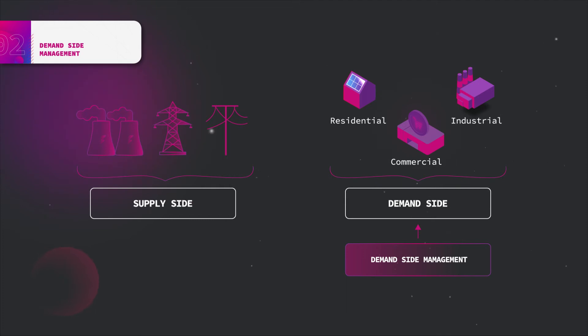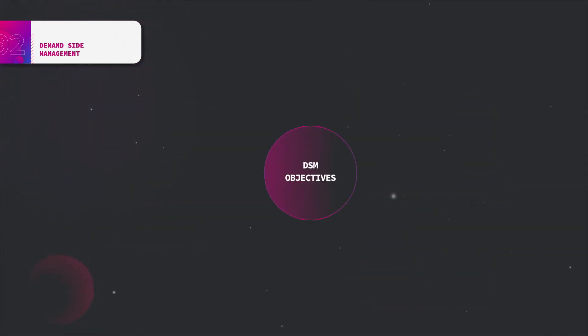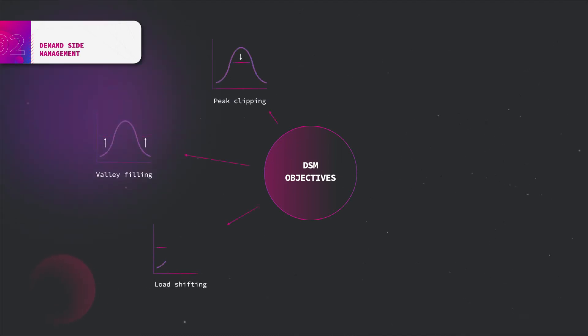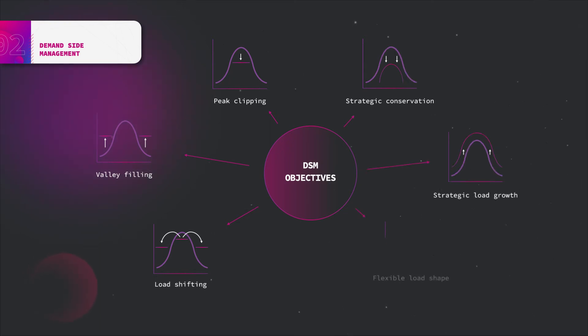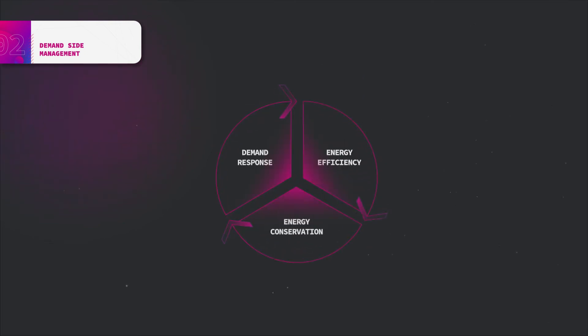Demand side management addresses all basic load shape objectives such as peak clipping, valley filling, load shifting, strategic conservation, strategic load growth and flexible load shape. DSM consists of three types of activities.